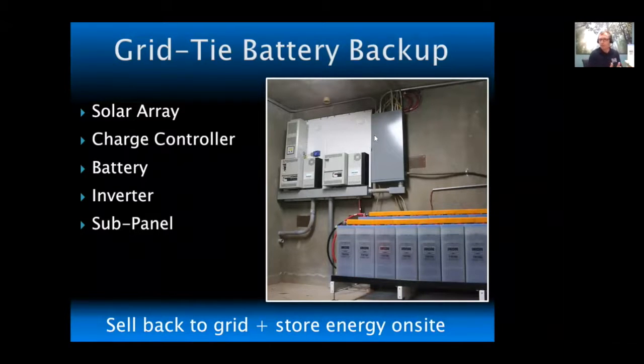It may not be all of the loads or all of the circuit breakers, sometimes half or less depending on the size of the house. But these are the circuits, lights, fans, refrigeration, maybe not the hot tub, but definitely the freezer and the pump, anything regarding health, safety, and welfare that will be isolated on this critical load subpanel. When the grid goes down, the inverter is able to output energy directly to this critical load subpanel and keep all of those circuits energized, whether the grid is present or not.